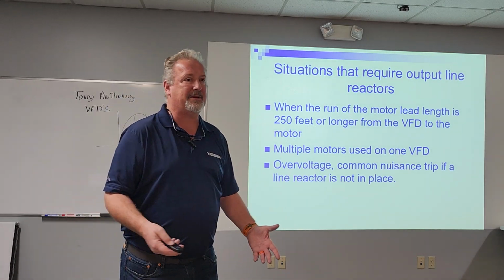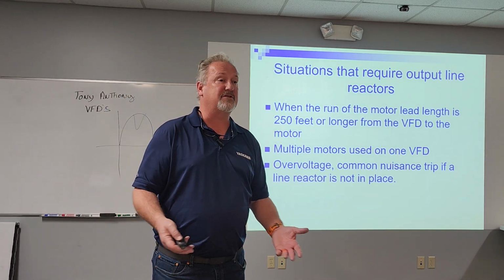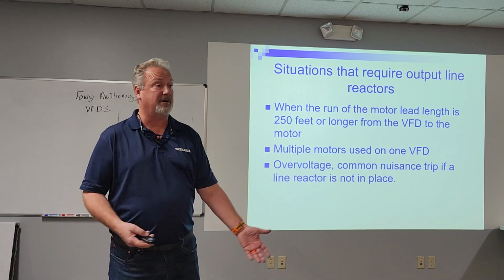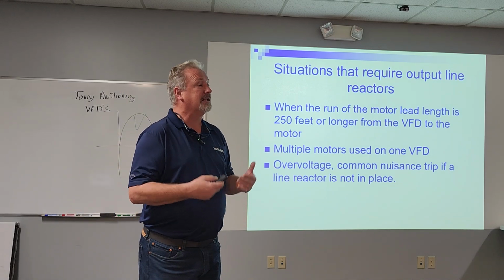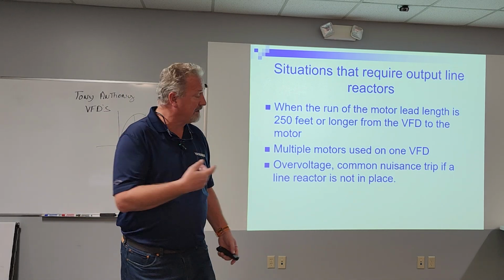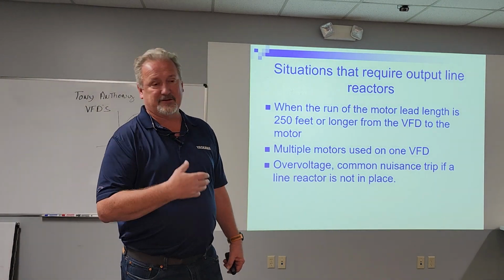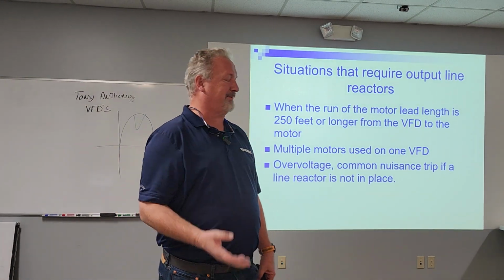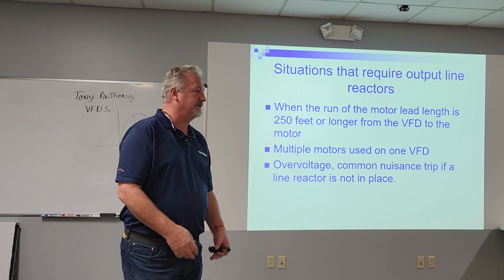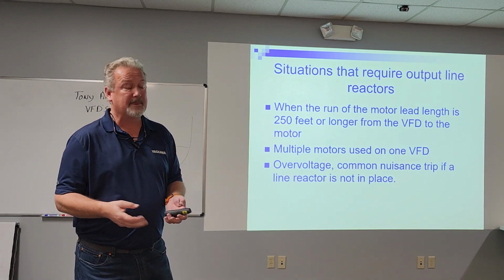We get the calls all the time. Hey, I got this motor. Can I run a drive on it? Or I'm at 200 foot. Do I need to put a load reactor on it? It really depends on the motor. It depends on the insulation in the motor. There's a motor manufacturer out there, off the record, they say you don't need anything. Our motor's good up to about 500-600 foot. That's how good their insulation is.